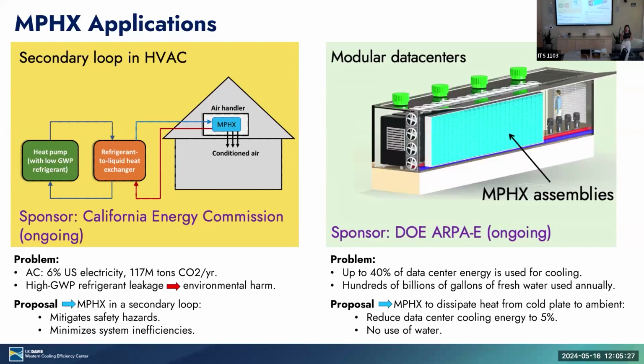So there's a shift right now towards moving to low and even super low GWP refrigerants. The issue is that they have safety concerns, since they are highly flammable, which would be dangerous to have inside a building with other people. So the idea is to have the heat exchanger with the low GWP refrigerant outside the building, and then employ a secondary loop, where our MPHX would take place.